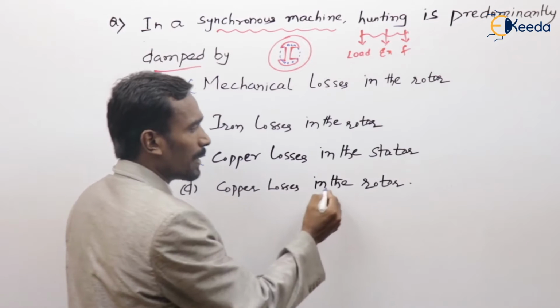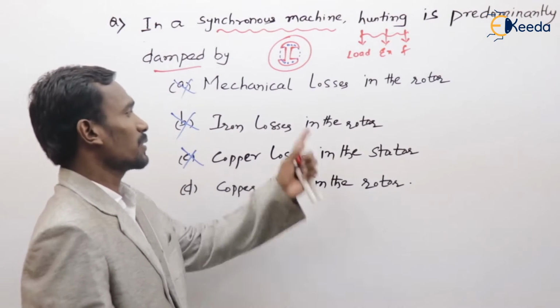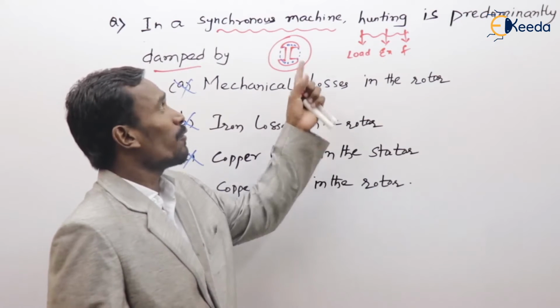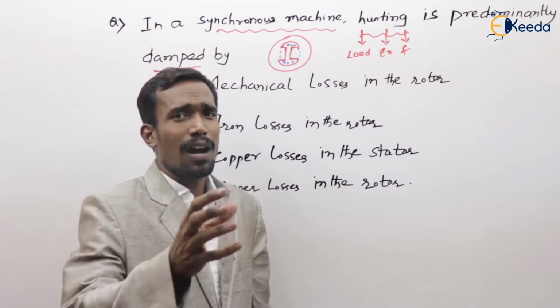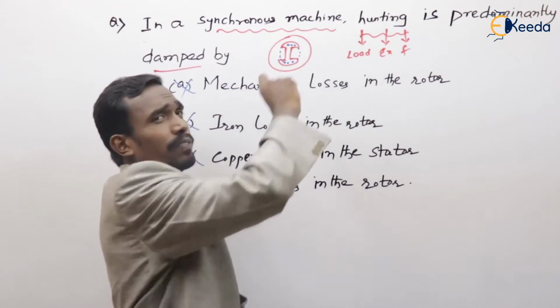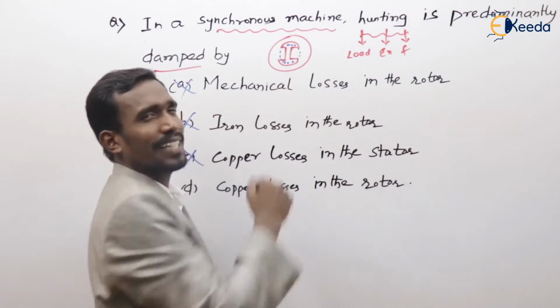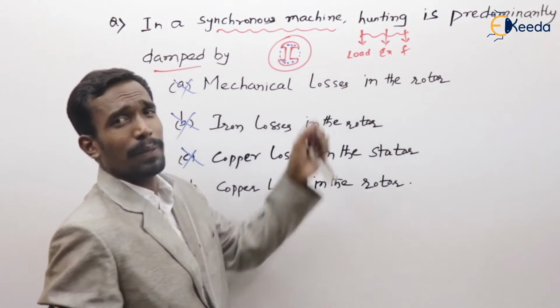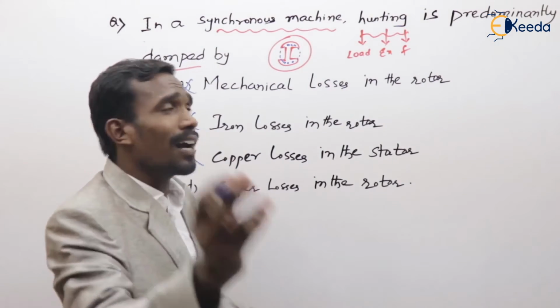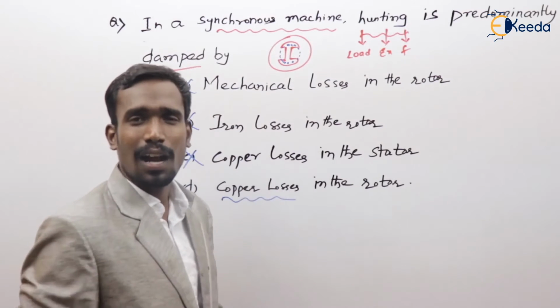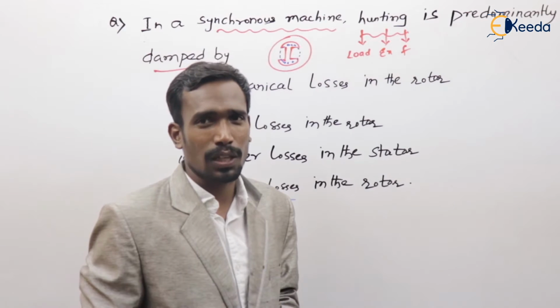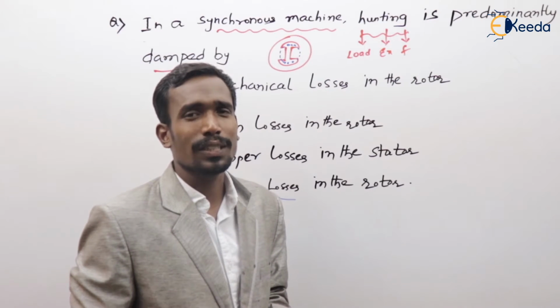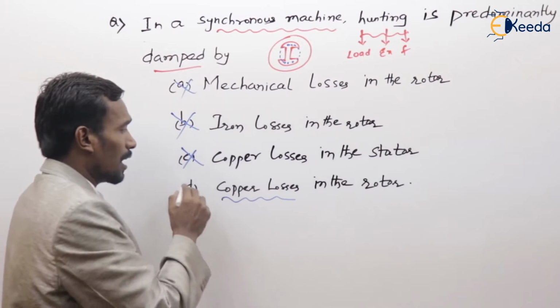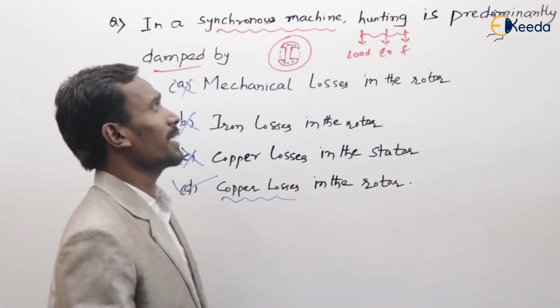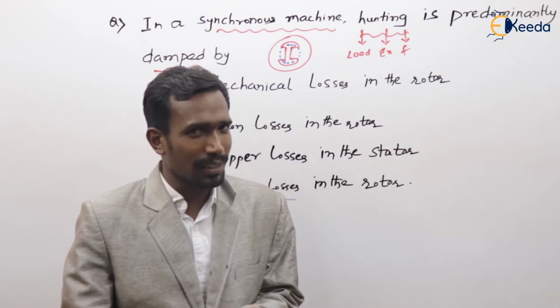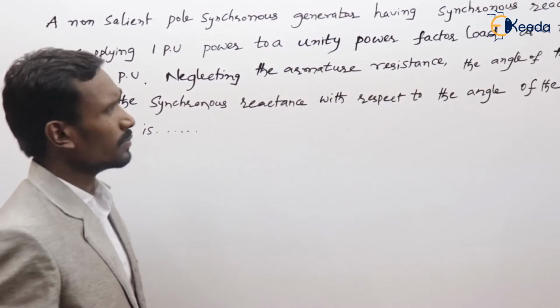And the next one, copper losses in the rotor. Yes, of course, this is the correct answer, because the winding is placed in the rotor, and because of the unevenness, damping torque is produced when current flows in the winding. When current flows in the damper winding, it produces damping torque and also copper losses in the rotor. So what is the answer? The copper losses in the rotor predominantly damp out the hunting phenomenon. Right, next question.